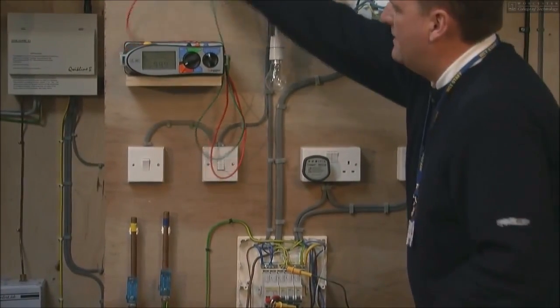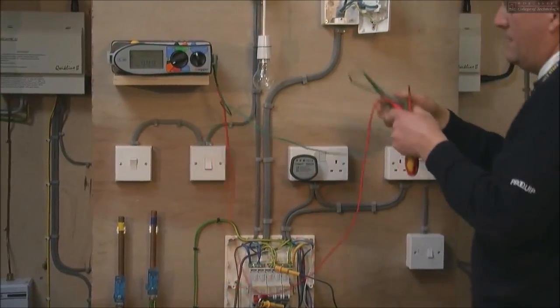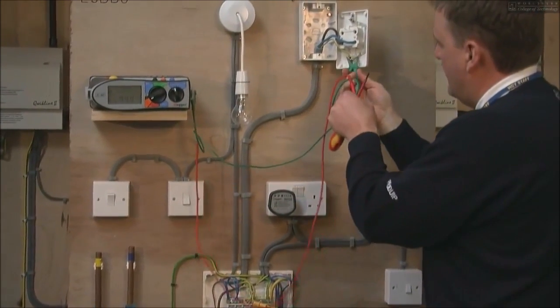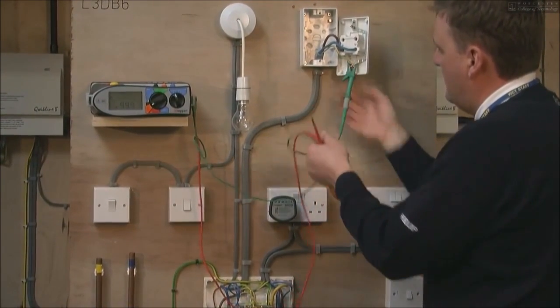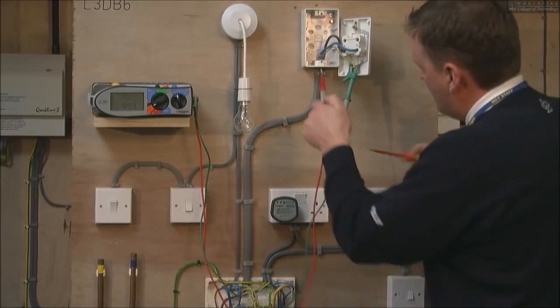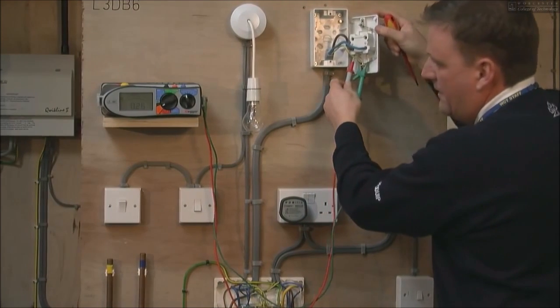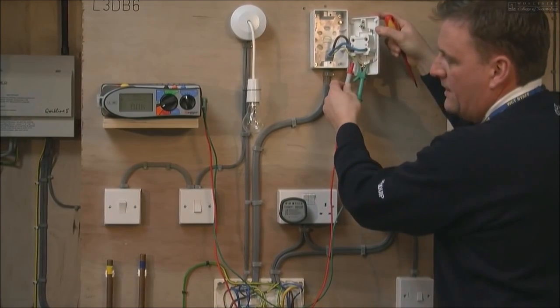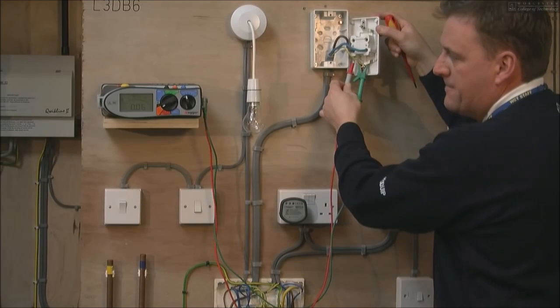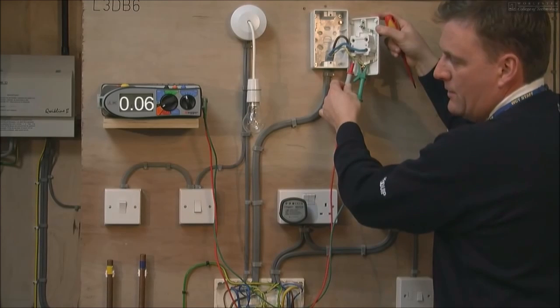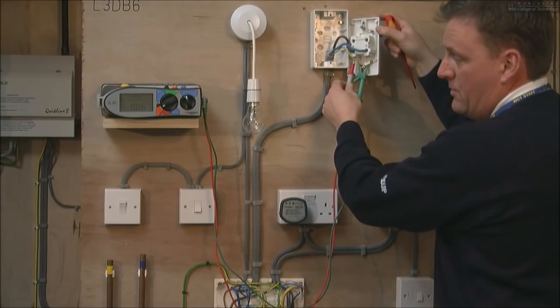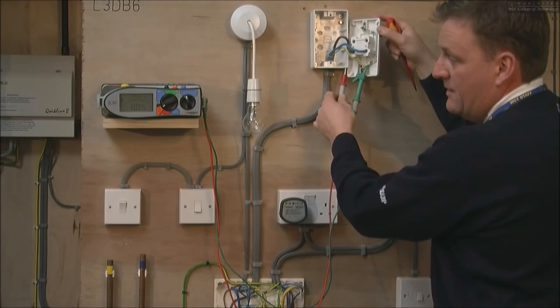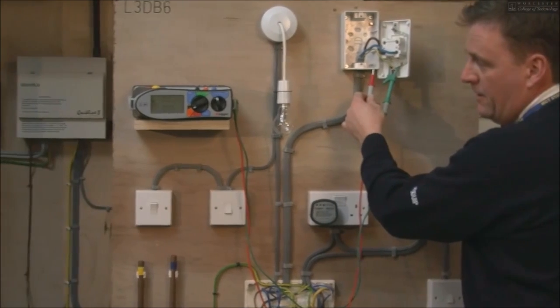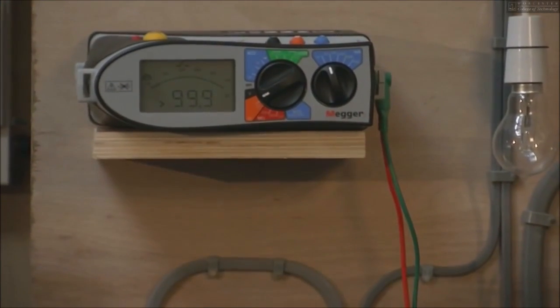We then take the test leads, clip them onto the earth terminal bar in the cooker switch, like so. As you see, we have a little bit of resistance there, and that's showing continuity. If it wasn't showing continuity, if it was an open circuit or broken circuit, we would get greater than 999 appear on the tester, like so.